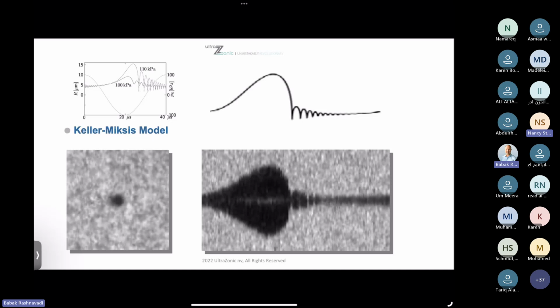So this Professor Keller and Professor Miksis, what did they find out? They said, hey, we have a cavitation bubble, and every single cavitation bubble always has the same transmission. It's actually what you see above. It looks like a signature. Every cavitation bubble always has the same signature. That means it grows, it collapses, and then you have the shock waves. So this little spike that you see in the signature is really the cleaning of your instrument.